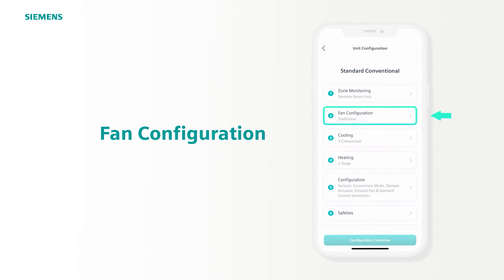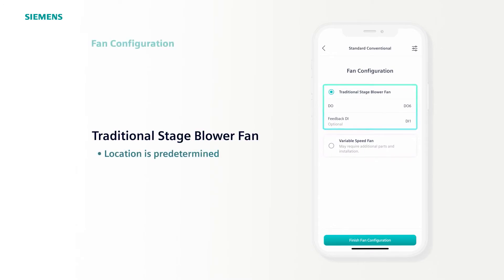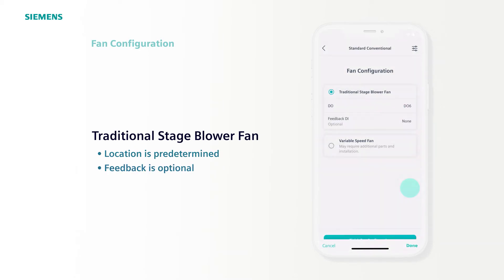Next, select Fan Configuration. If you've selected traditional stage blower fan, it is predetermined on DO6, with the optional fan feedback on DI1. As the feedback is optional, simply tap it and choose None if you do not need it.